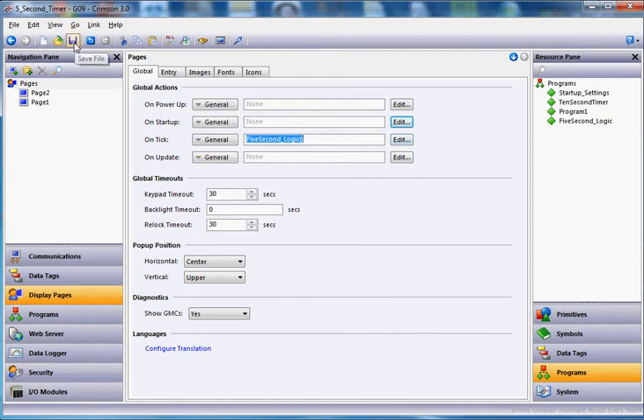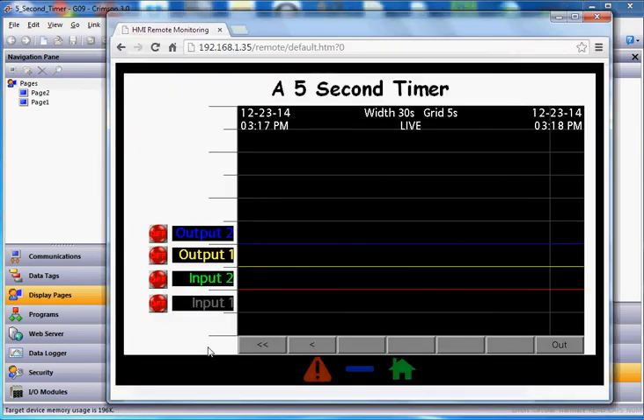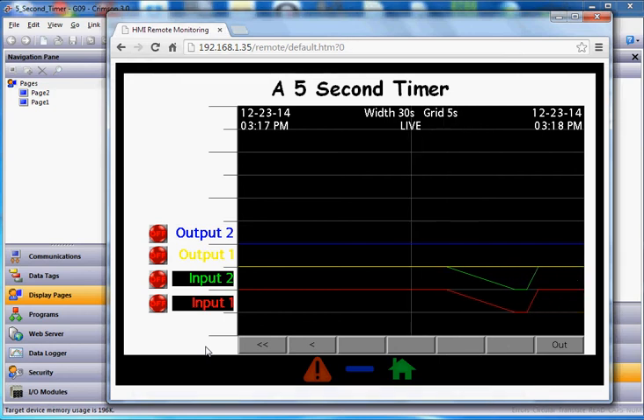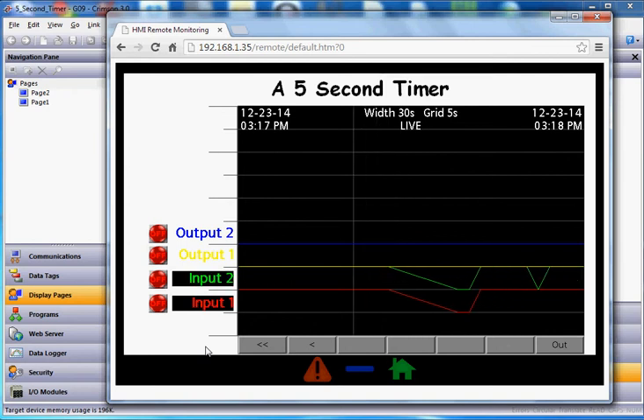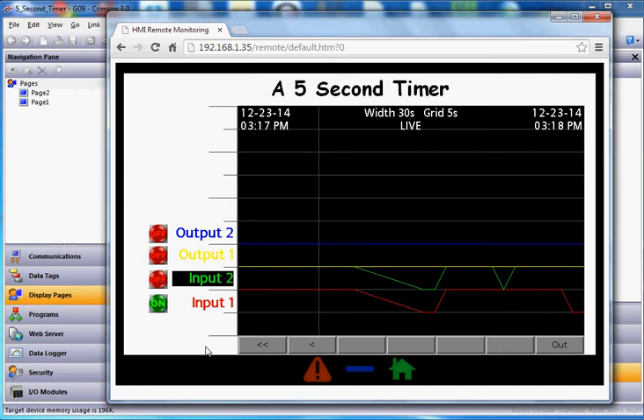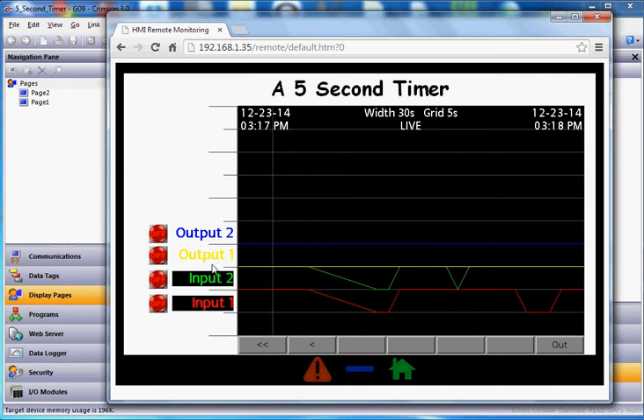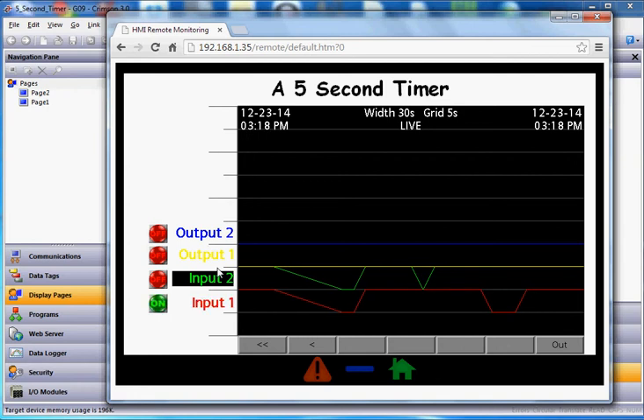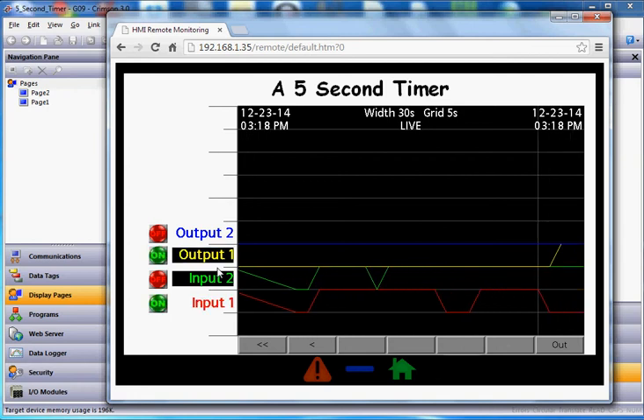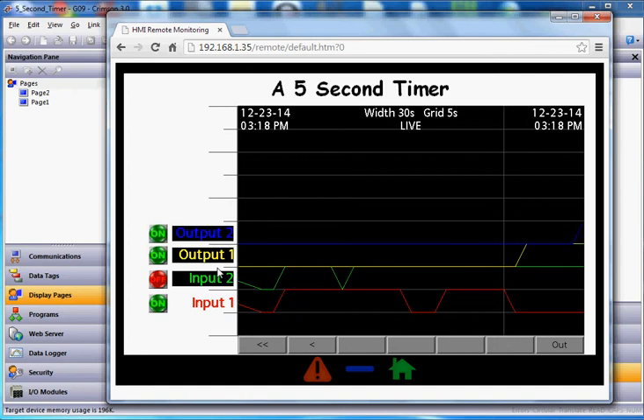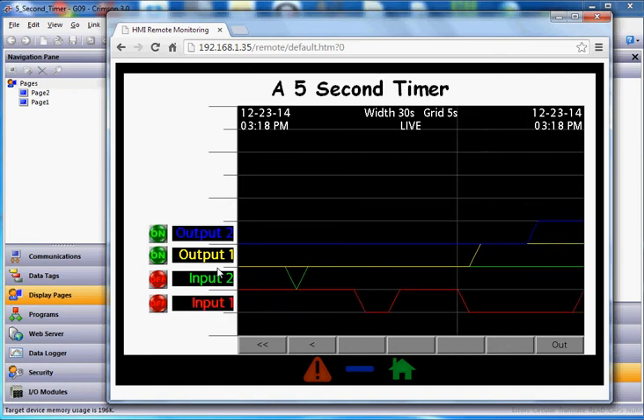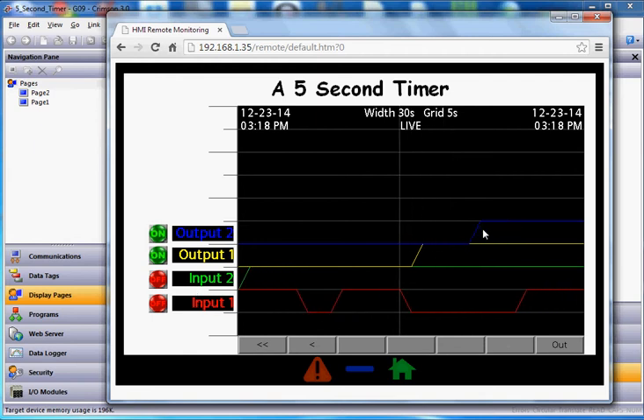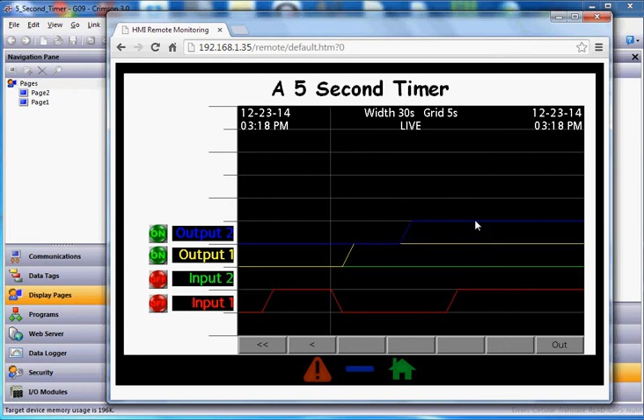So that should work okay there. Let's just test this and see what happens. So I'll save my program and we'll download it. Let me go ahead and open up the web server so you guys can see the actual status of the input stuff here. So if I turn on, I think this is input two. Yeah, we're not doing anything on input two, that has nothing to do with this. Let's try input number one. So if I hold down input one for a few seconds, you'll see nothing happens. I want you to pay attention to these outputs right here. So I'm going to go ahead and hold down input one again here, and you can see here, after five seconds, output one went on, and there goes the other one. So you can see that's working, I got this graph here a little backwards. But you can see here that the outputs both went on right here, but they never went off.